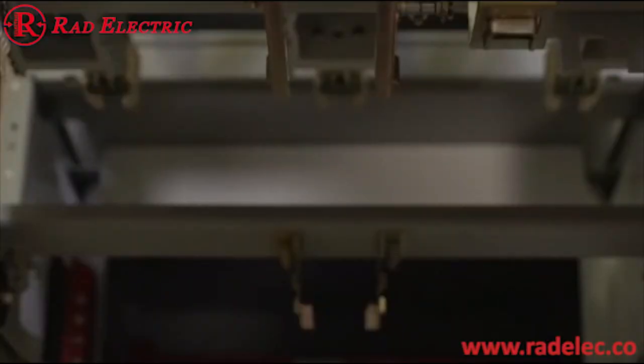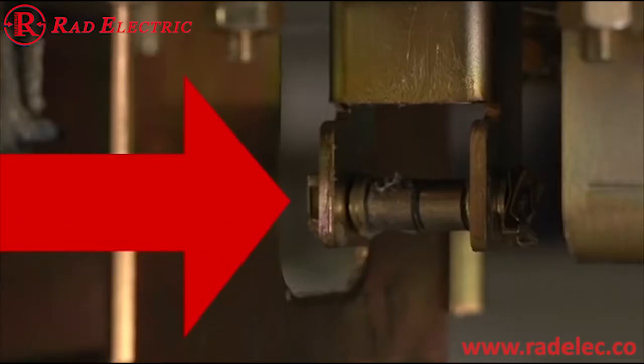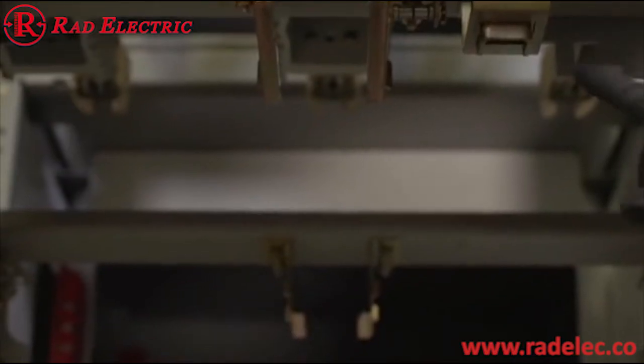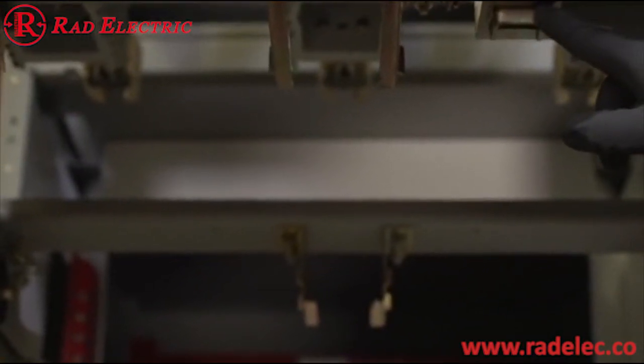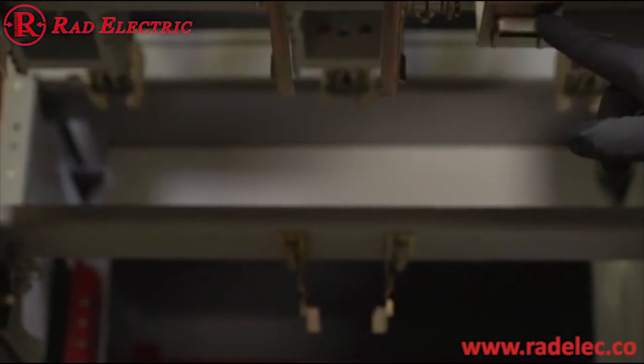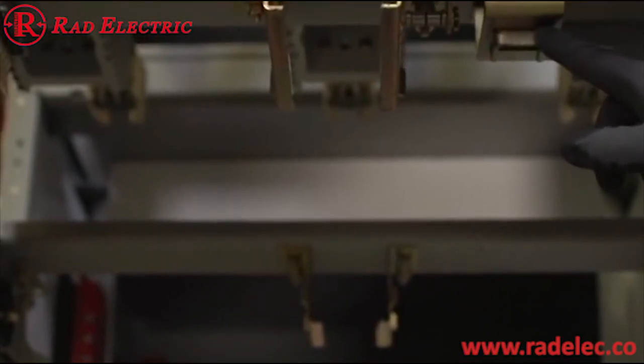Let's take a look at the important components found on the bottom of the circuit breaker. This is the trip-free interlock. It prevents closing the circuit breaker unless the circuit breaker is in either the connected position or in the test position. The trip-free interlock interacts with the sliding cam plate on the racking mechanism. This is the closed circuit breaker interlock. It prevents access to the racking screw when the circuit breaker is closed.